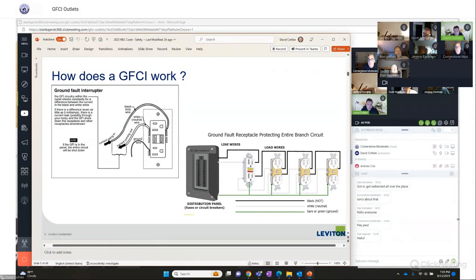The bottom right illustration shows a diagram coming out of your load center. A circuit is a wire coming out. As long as you lead with the GFCI on the circuit, you can protect other devices downstream for ground fault circuit protection. The code says there's really no limit on how many receptacles you can have after the GFCI, but typically electricians set a limit. I've seen 5 or 6 receptacles, and then they call it quits.